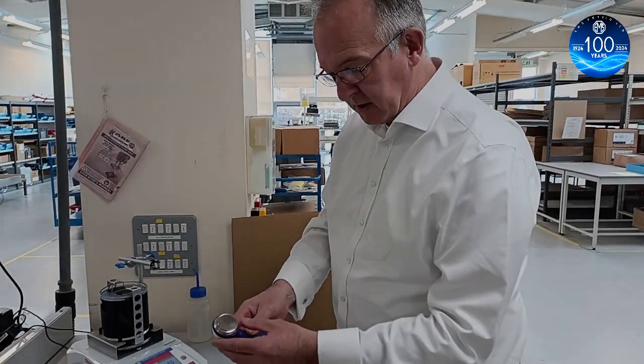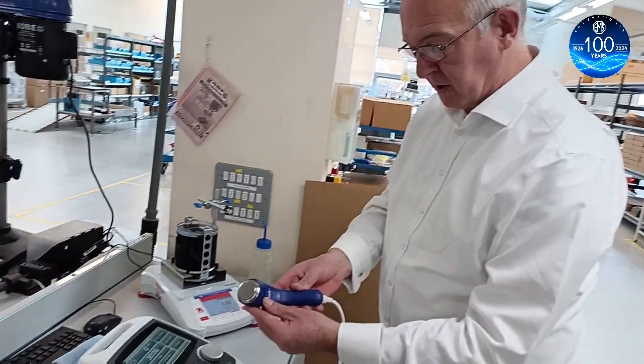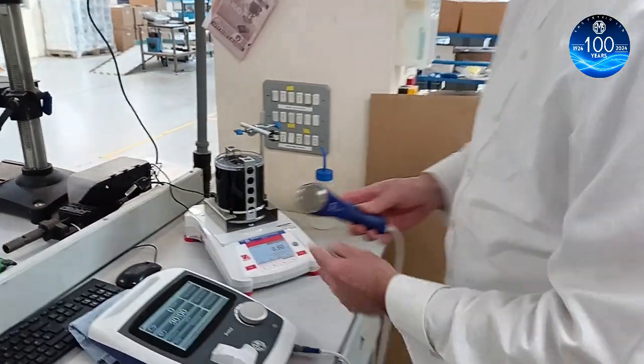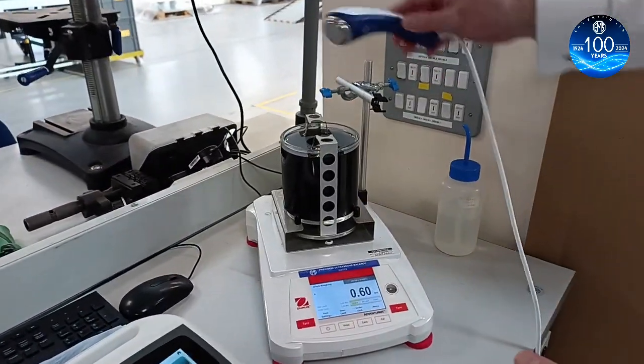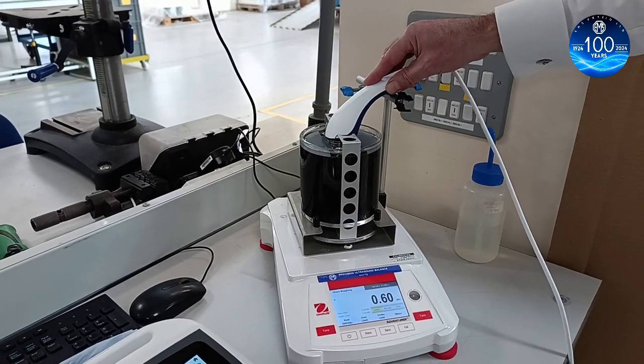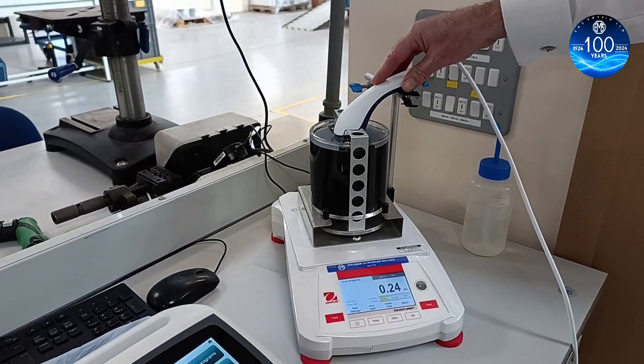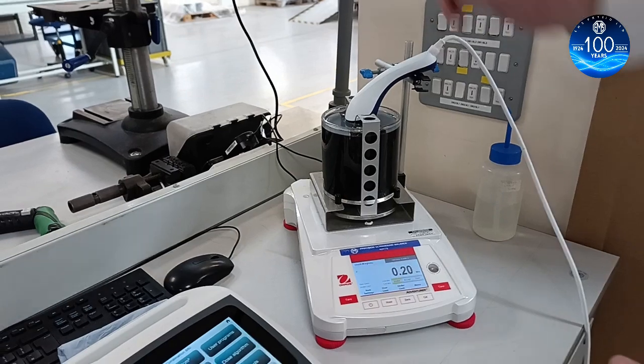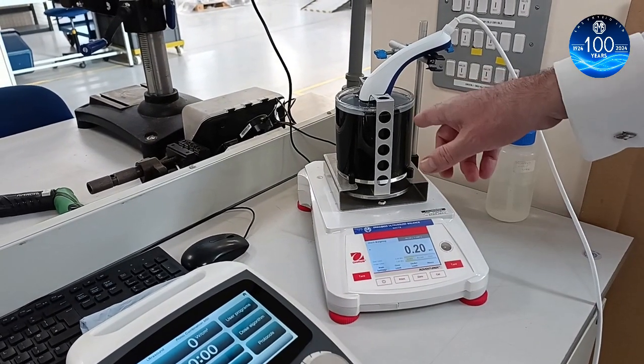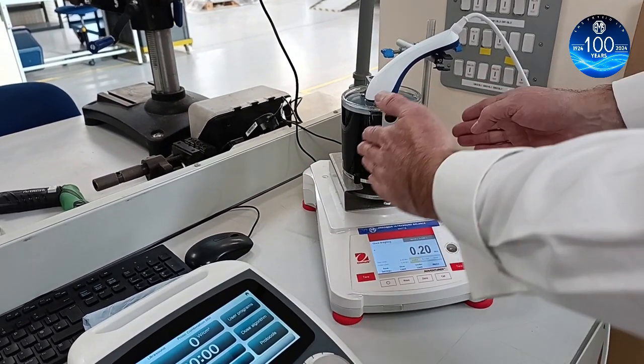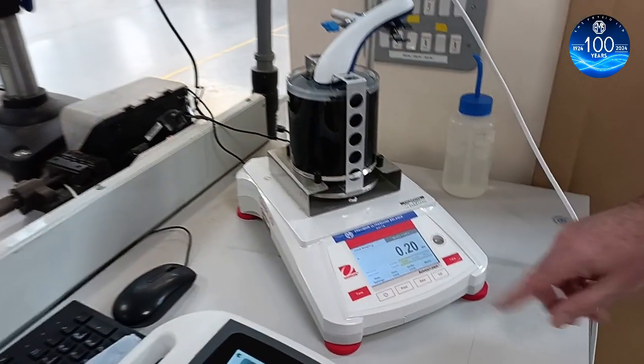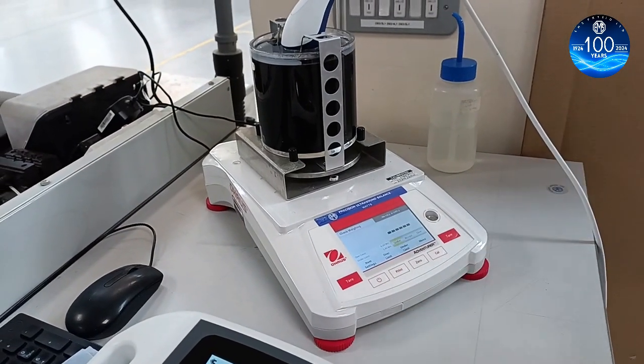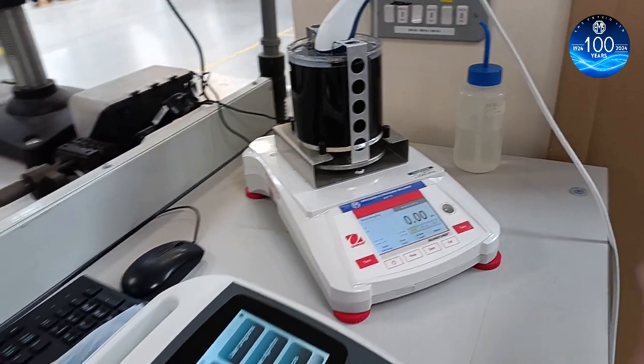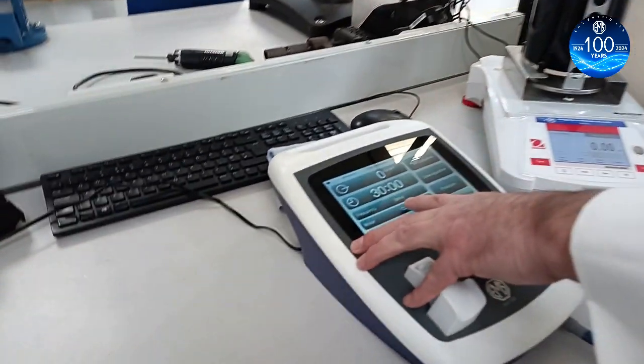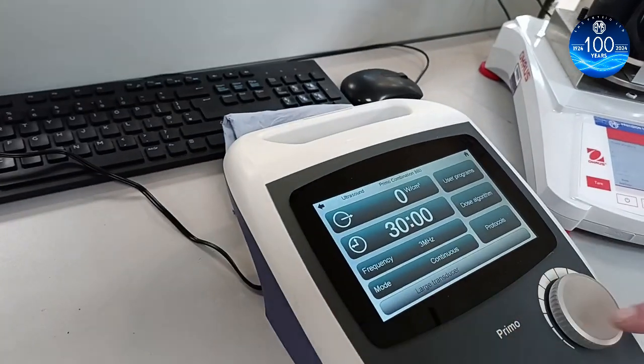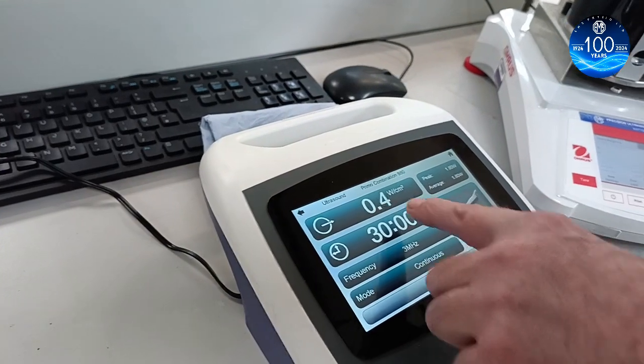The steel and crystal assembly has now been fitted to the transducer. We're going to test the output on this precision ultrasound balance. It sits on there so that the transducer is in contact with the water, and there's a reflecting target inside that force balance. You can zero that, and we're using 3 megahertz in continuous mode.